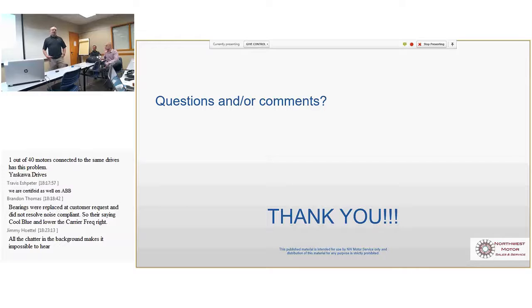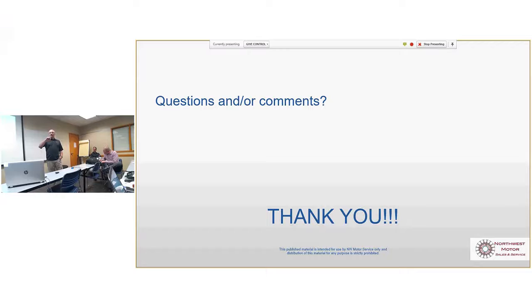One other thing, with the online testing stuff, we can also do transient analysis, a special feature where we can see contacts closing during a startup. It's doing a lot of samples per second, so it's really good resolution. I can record a soft start or a VFD starting and see every step along the way, and make sure it's really operating the way you programmed it. If you have weird problems like bad contacts in a starter, the test will differentiate.